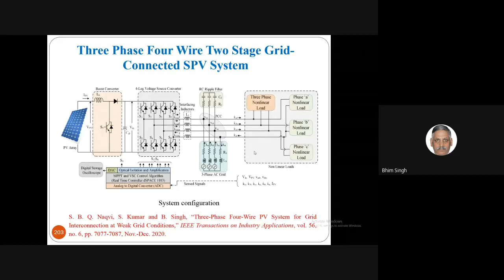Sorry, anyhow, there was a call. So we extended it even for 3-phase 4-wire, so that neutral current compensation can also be provided along with this boost current. So we have taken all power quality issues along with the solar generation and taken another algorithm. Here we are able to provide neutral current compensation under load removal and load addition, and even the grid currents are still maintained sinusoidal.